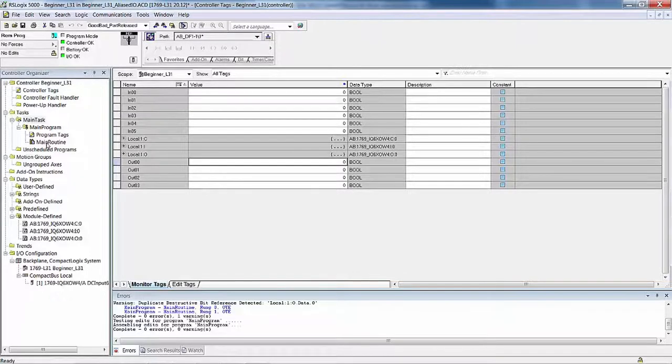You'll find that out. So the upshot of this is a MicroLogix controller, a SLC 500 controller, a PLC5 controller has one program and one tag database, if you want to call it a tag database. It wasn't called that back then, but it is the same thing as a tag database. And those tags are universal to the entire controller and to the one and only program.